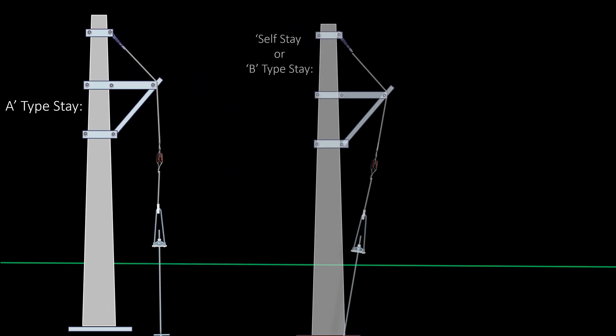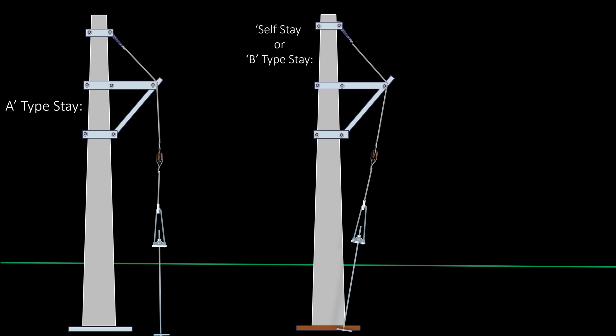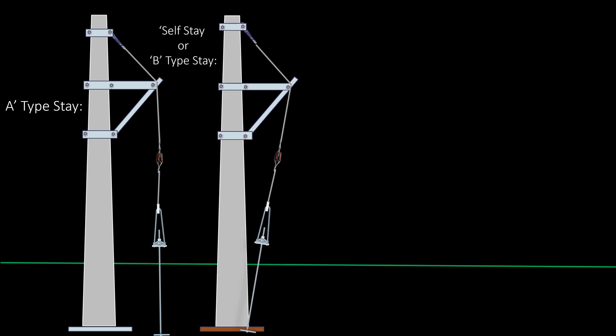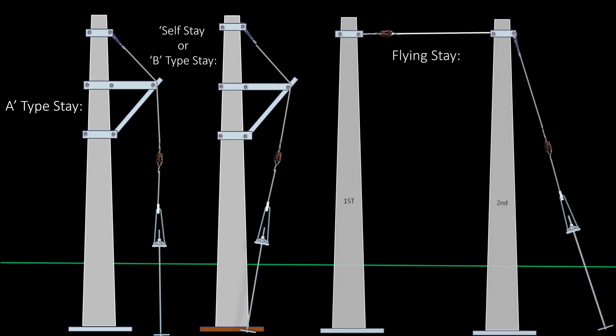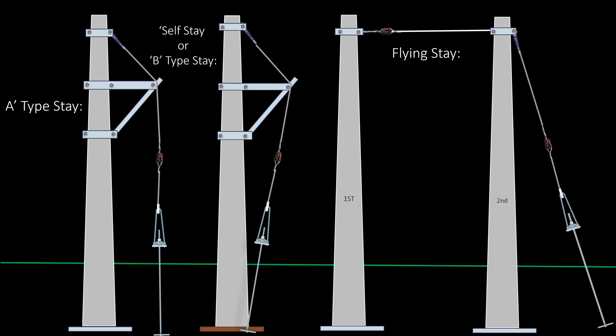Self-Type Stay (also called B-Type Stay): When there is no space for a stay, the lower portion of the stay wire is clamped by a stay clamp to the lower portion of the pole. Flying Stay: When the line is on the roadside and there is no space for a stay, another pole or pole piece of sufficient height is erected at the opposite side of the road, and a stay wire is tied up between the pole and the pole piece to give tension to the second pole or pole piece.